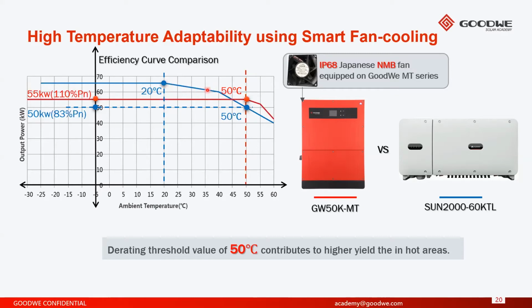Whereas on their data sheets, they say that they start derating from anywhere between 30 to 35 degrees. So there is a 10-degree difference in what they're stating on their data sheets. So that's one of the things to look out for when selecting or choosing your inverter for your commercial installations.